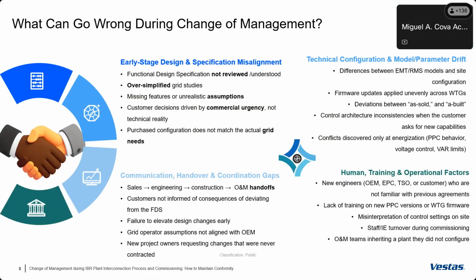The first one is early stage and specification misalignment. At Vestas, we have something called functional design specifications, and I guess other OEMs call it something different. This document captures the control architecture, the strength of the grid, and all the Vestas-specific control functionalities on IBR units the plant will require. Of course, that needs to be connected with the grid studies and the specifics of the grid.